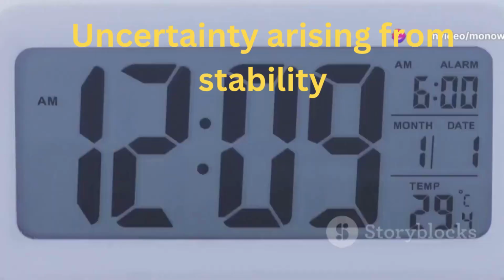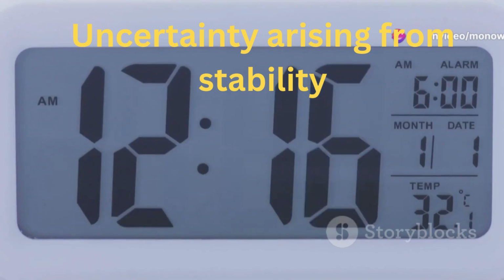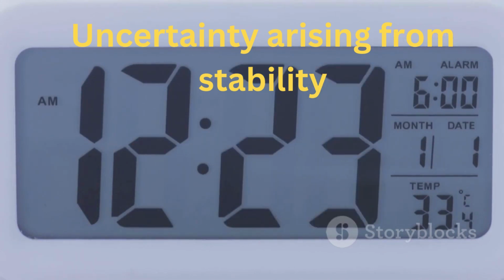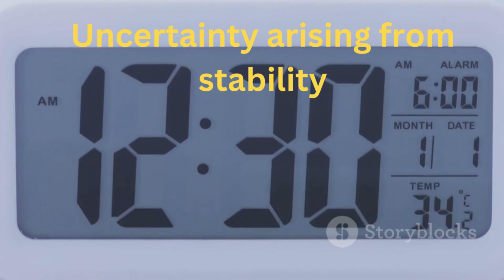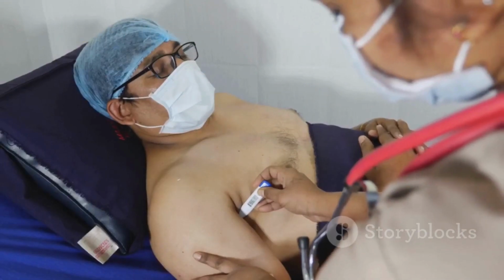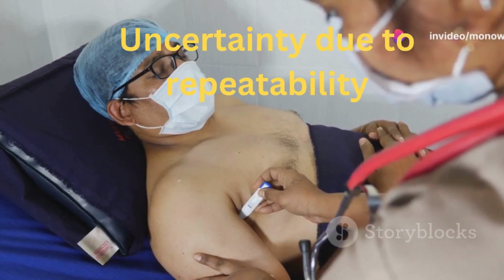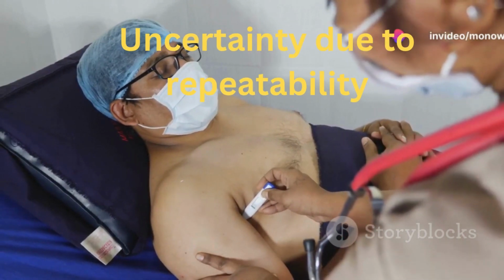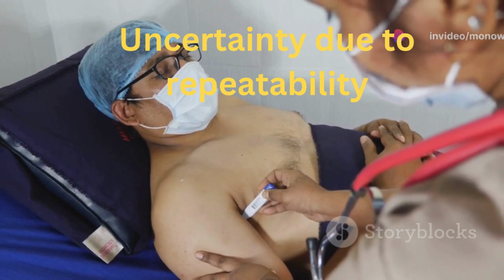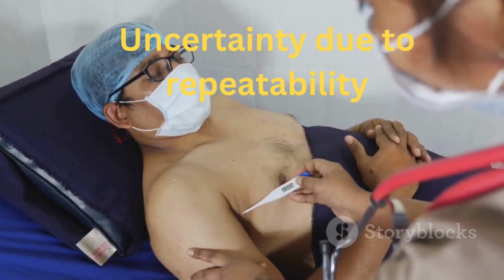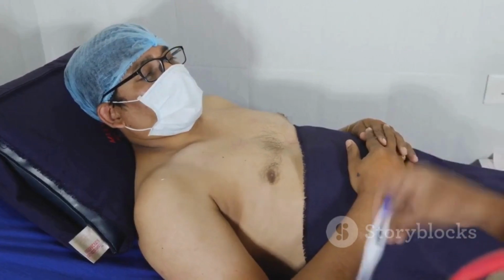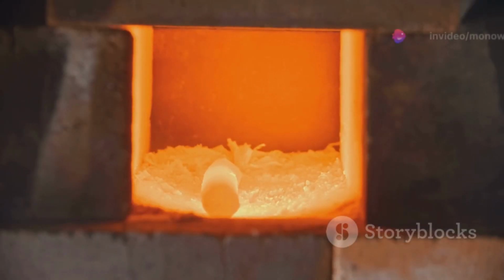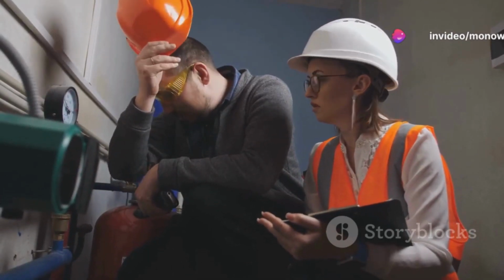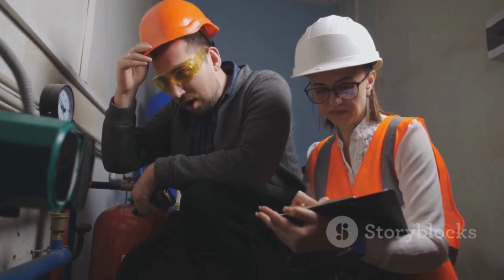Other factors include the stability of the thermometer over time. A thermometer might give accurate readings today, but what about a month or a year from now? This is where periodic recalibration comes into play. Then there's the matter of repeatability, the ability of the thermometer to give the same reading under the same conditions. If the thermometer gives different readings each time, it introduces another layer of uncertainty. Let's not forget the influence of thermal conduction, convection, and radiation. These heat transfer modes can affect the thermometer's reading and introduce uncertainties.